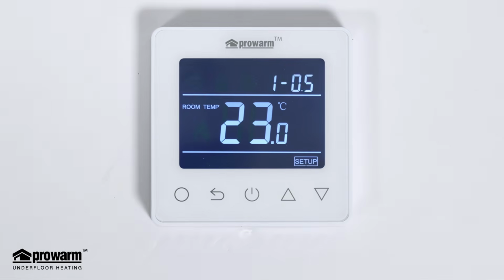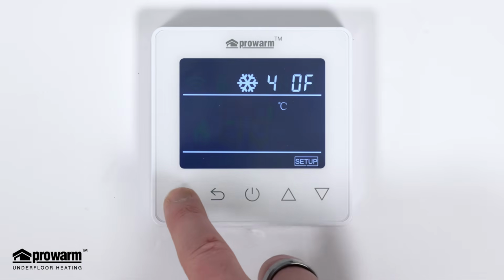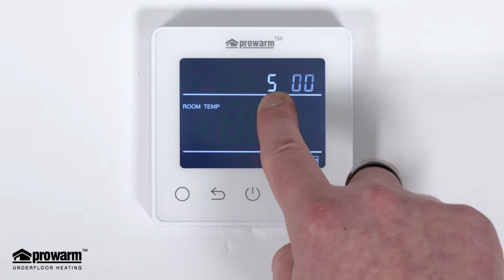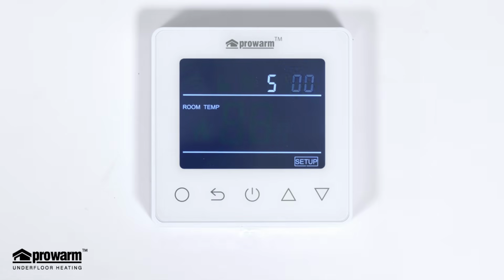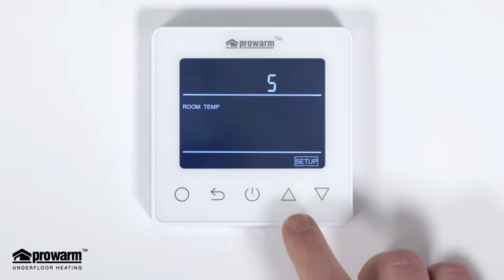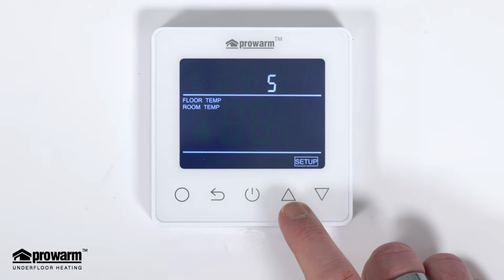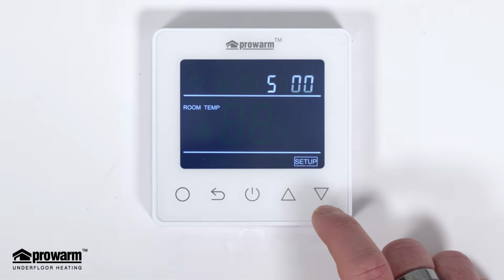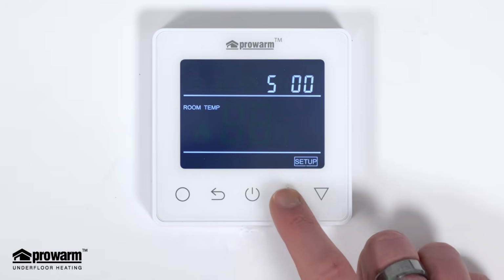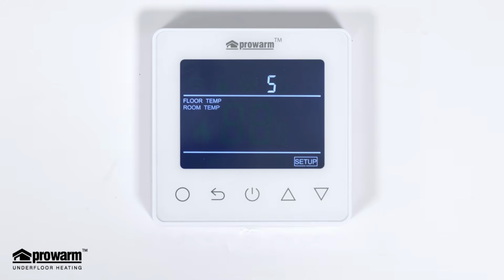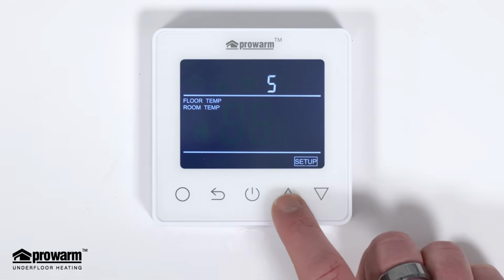Continue pressing the circle until the number on the top right reaches number 5. This is the sensor selection setting. Use the arrow keys to select the required configuration. 00 is for room temperature, 01 for floor temperature, and 02 for both sensors. We're going to select floor temperature.